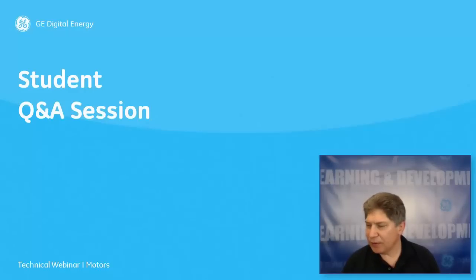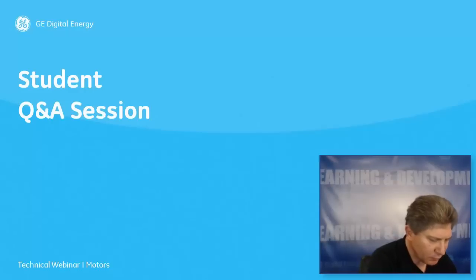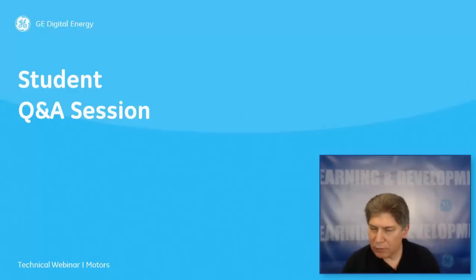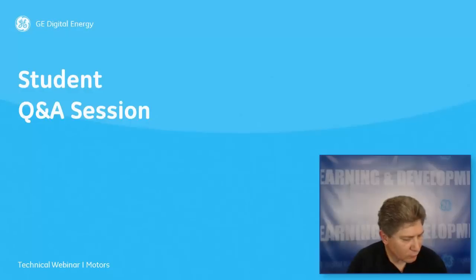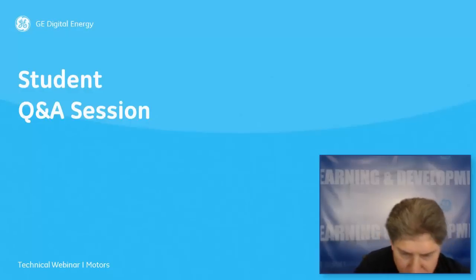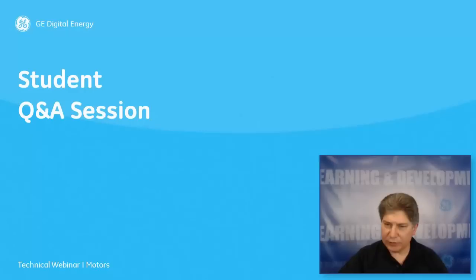Any other questions? George, this is Pat Kerrigan. Can you hear me? Yes, I can. Okay, I just want to comment on the last two questions. That twice the knee is based on all the calculations that you've done being based on AC symmetrical waves, and any kind of fault is likely to have a DC offset, maybe a full DC offset, and that saturates the CT in a different manner. Correct. So empirically, people use that factor of two because of DC saturation. It isn't quite accurate, but it's good for calculation, so that's why people do it.